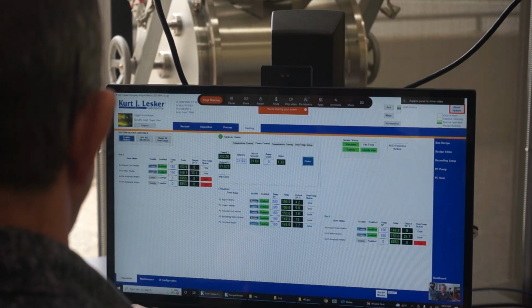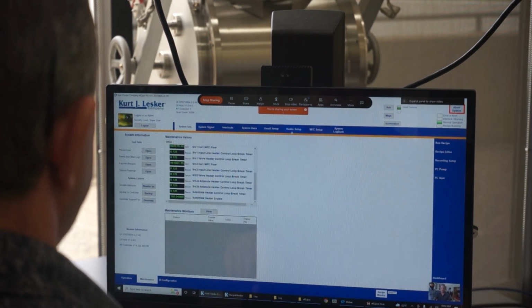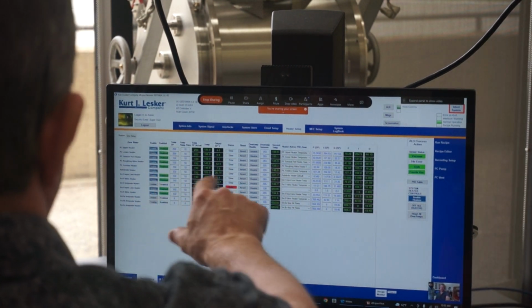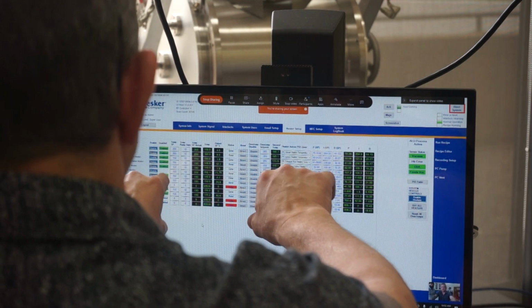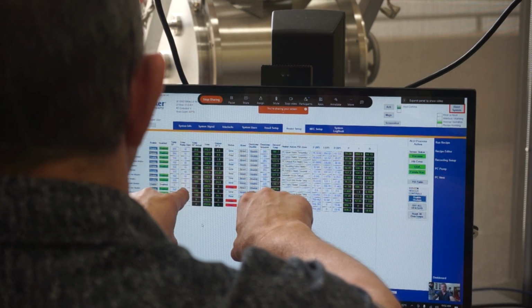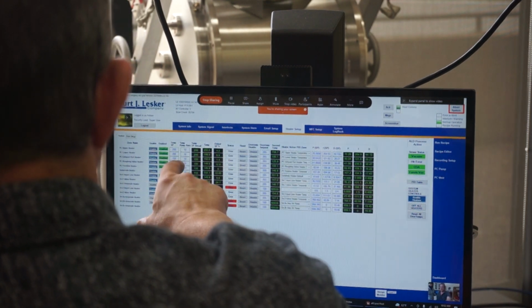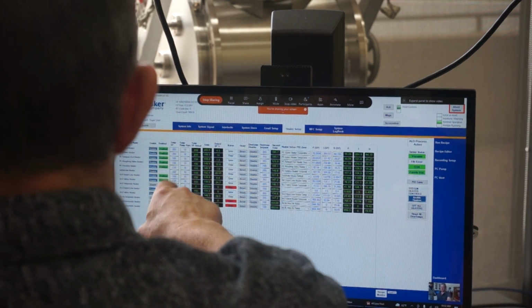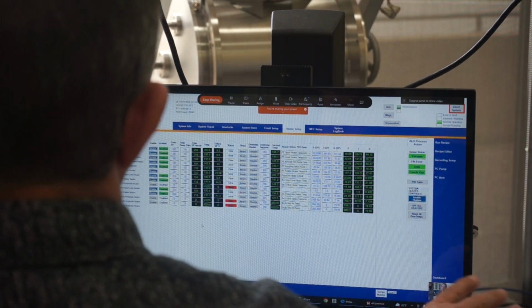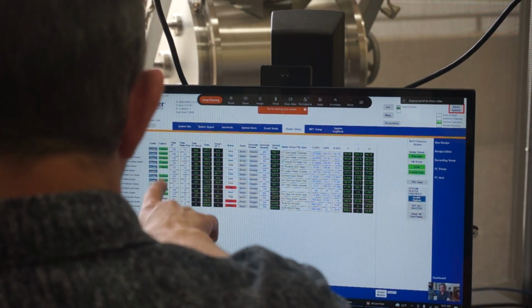This maintenance heater setup, you have your thermocouples reading. You have a ramp option if you want to control it for your system heaters, along with your substrate heater.